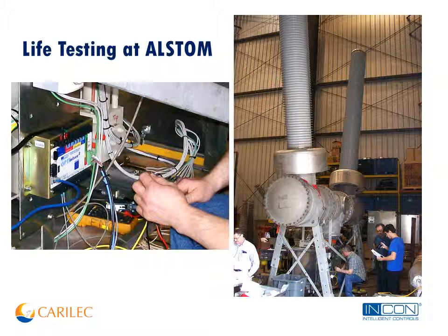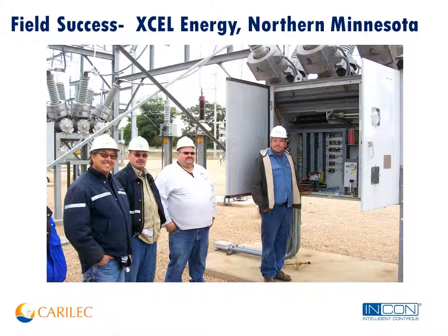Here's some testing that's going on presently at Alstom in Pennsylvania. This is a 550 kV independent pole operated breaker, and in the cabinet below is the optimizer, and they're very pleased with it so far, and they've tested it beyond 15,000 operations and all the vibrations and everything with it so far. They're very pleased. We've had a number of field successes.